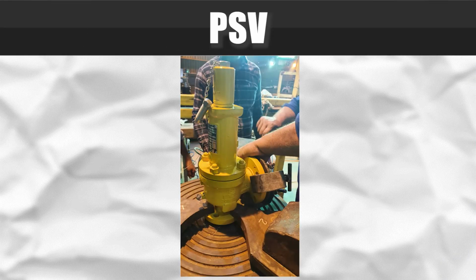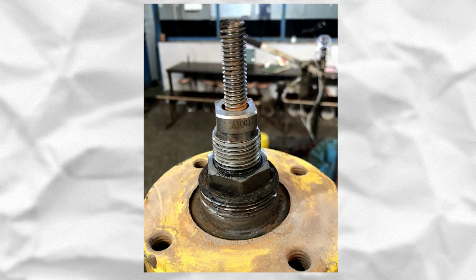due to friction. It is used to protect the valve against spark that may ignite the fuel flowing through the valve. The ball valve with an anti-static design is especially for fields like oil and gas, chemical, power plant, and other industries where fire-free operation is an important guarantee of safe production. The third type of valve is PSV or pressure safety valve. These valves perform mechanically. With the help of a spring and adjusting screw, we are able to assign a pressure set point to that. The time that the process pressure reaches its set point, the valve opens and the excess pressure releases out. This type of valve protects equipment such as drum, vessel from overpressure and blasting.